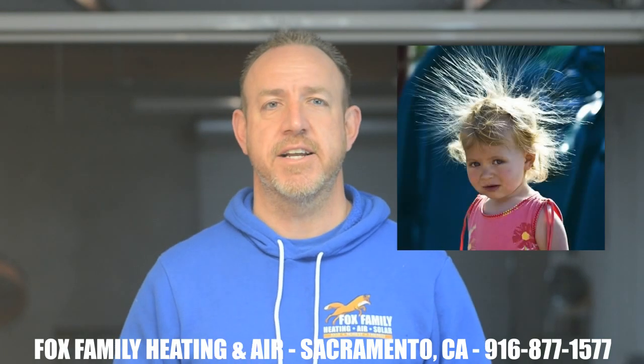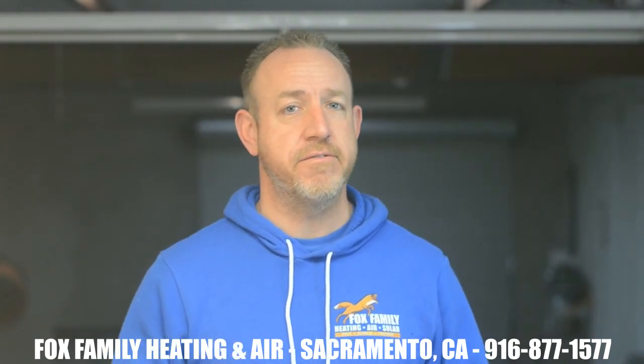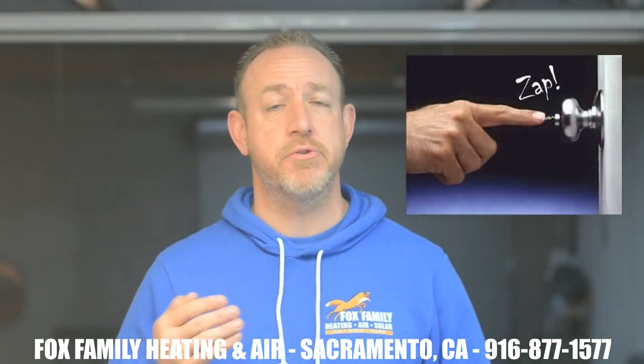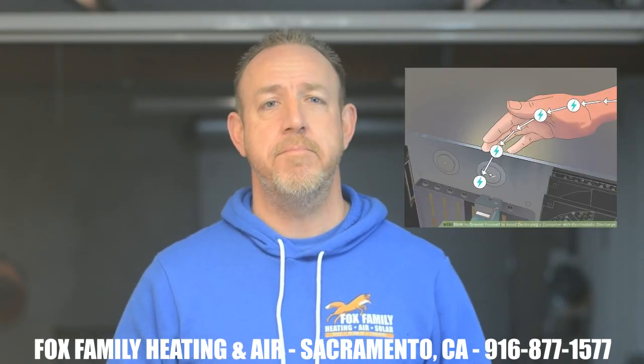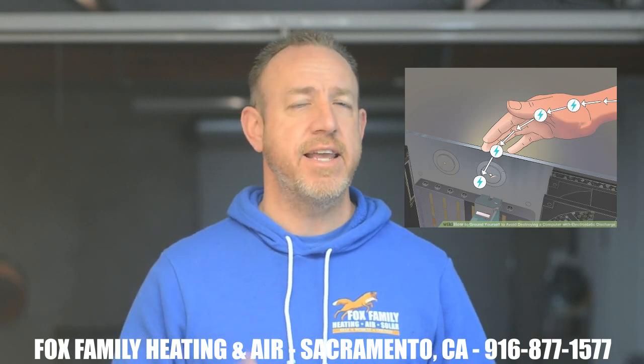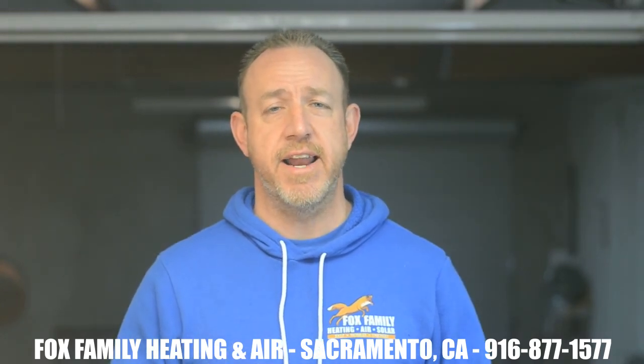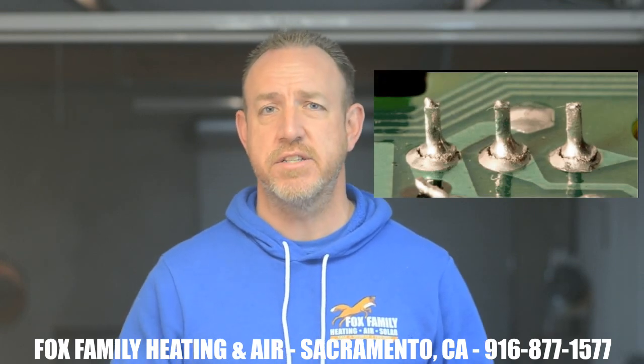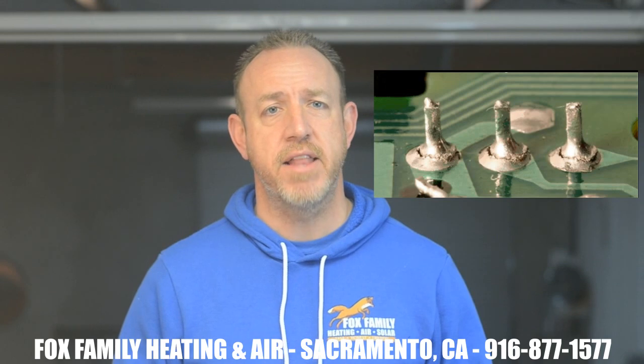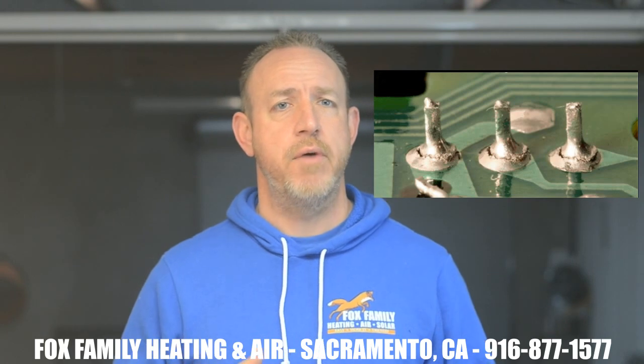Next, let's talk about static electricity. Careless or unsuspecting technicians who walk across a carpeted floor to get to their furnace can build up more voltage on the body than it can store. As a result, that voltage will need to be transferred to the next piece of metal it comes in contact with — and you don't want that to be the metal on a control board. ESD can even develop after you've grounded yourself to the furnace the first time, as standing on carpet can create that static very easily. The damage is done to control boards when electrostatic discharge hits the board, affecting very thin insulating layers within the board's transistors, relays, switches, and solder joints.